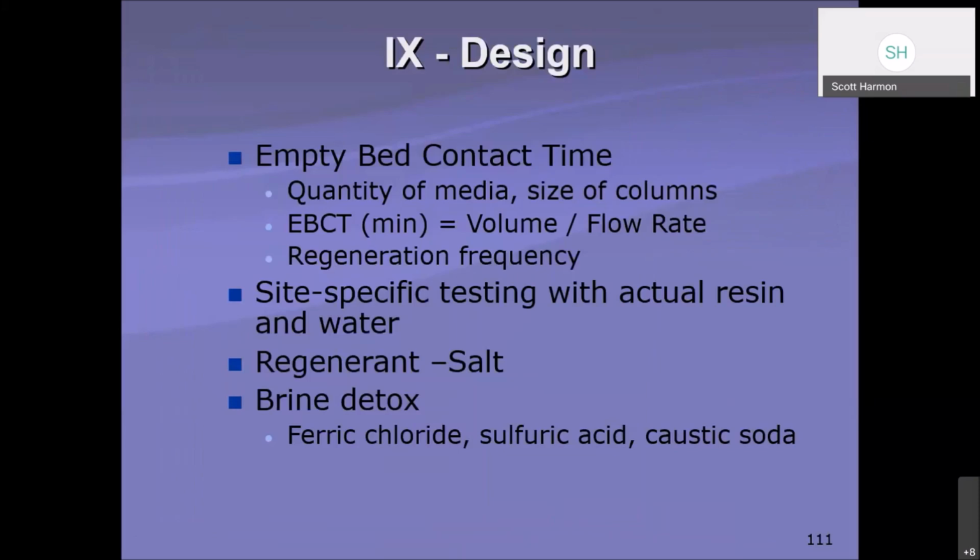The design of this particular type of system is based on the empty bed contact time, much like when we talked about it in the filtration part earlier. Quantity of media, size of columns, flow rates, flow designs, right? Specific testing of the water. So when they're designing this, the source water would be tested. What type of regenerant or salt you're going to use, how you're going to detox your brine, what you're going to do with that, right? And there's some other chemicals that could affect that detox as well.